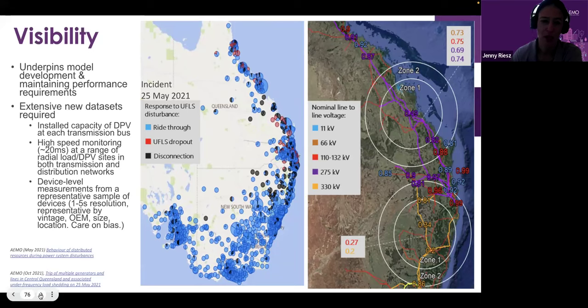The red bubbles are ones disconnected by under-frequency load shedding, triggered in response to this very severe under-frequency event, but in those places it was disconnecting a lot of distributed PV as well as load. So we have another piece of work looking at how to improve that under-frequency load shedding design so it's not tripping off generation during an under-frequency event.